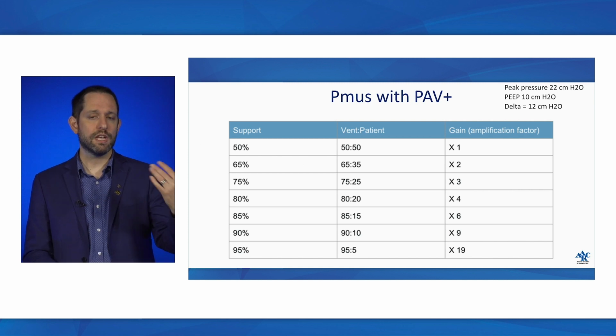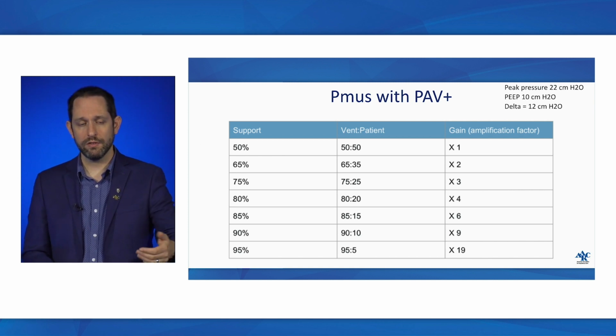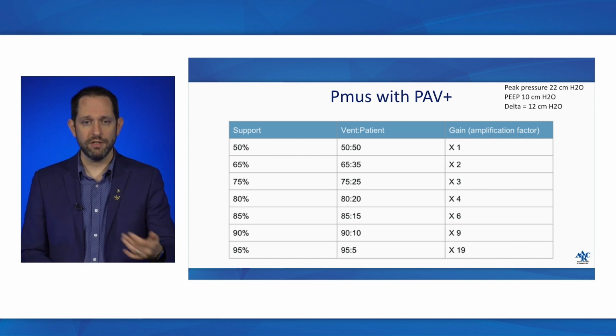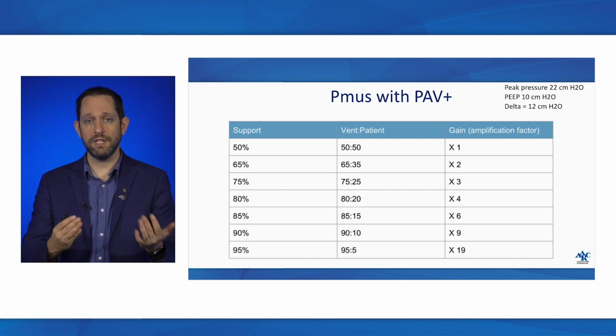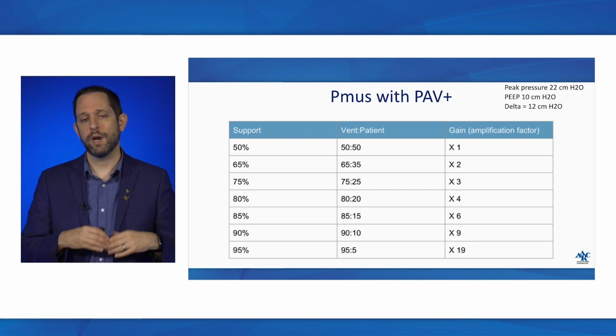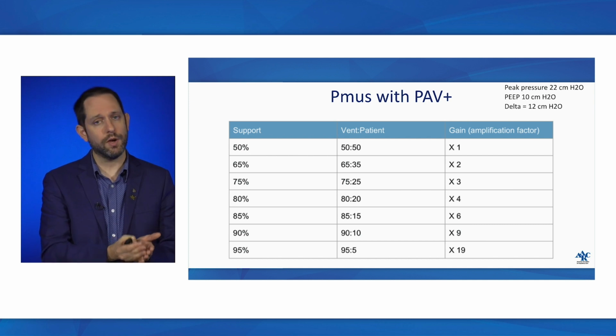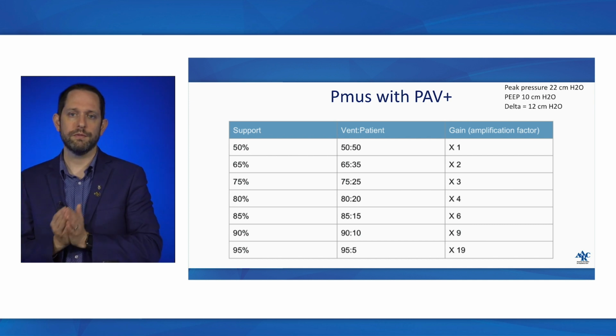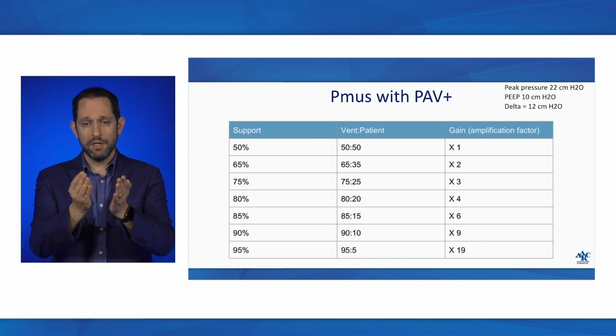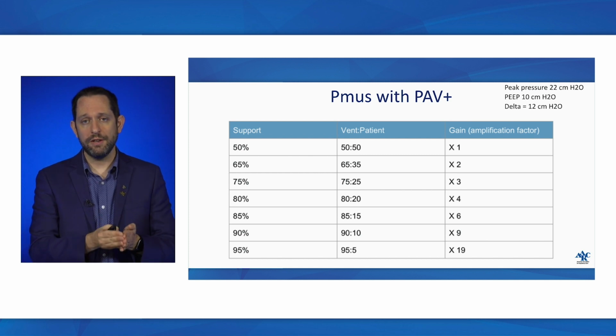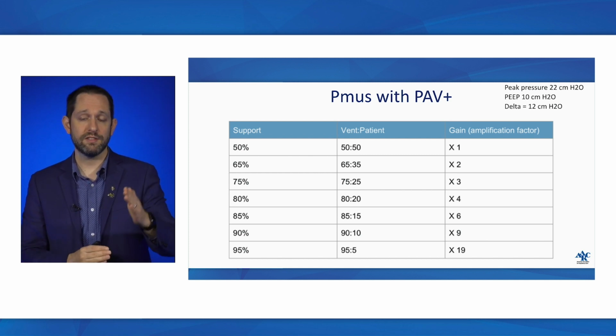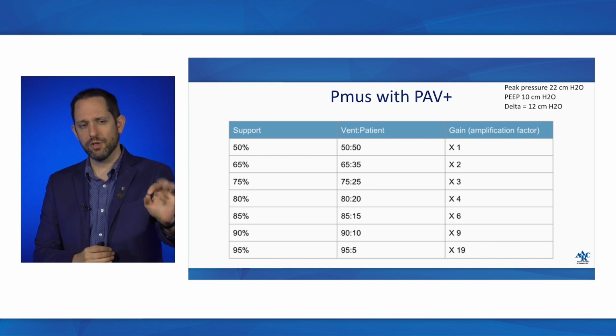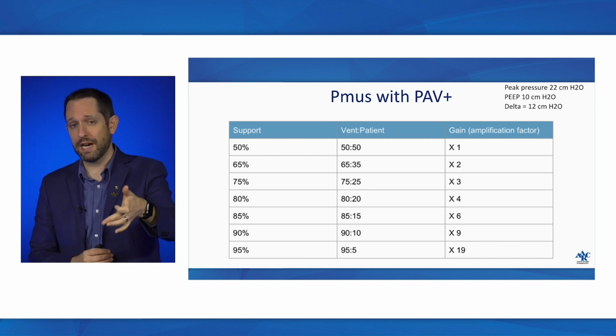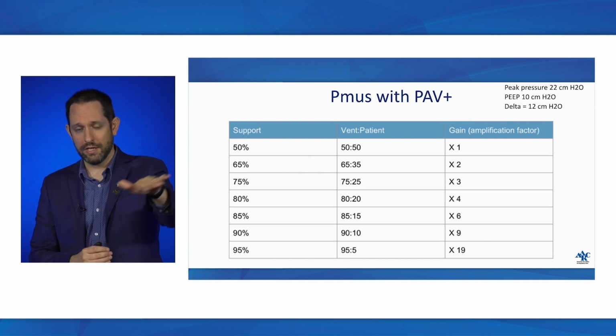Now, you can calculate it for all types of levels. So 50%, as I mentioned, you're matching the patient's 50 to 50. It's a shared ratio. So whatever the ventilator is doing, in this example, 12 centimeters of water, the patient's doing 12 centimeters of water. If 12 was on the screen and your patient's percent support was set at 65%, and I've specifically chosen these PAV levels because they increase the gain or the amplification factor, typically by 1 until you get into the higher levels.